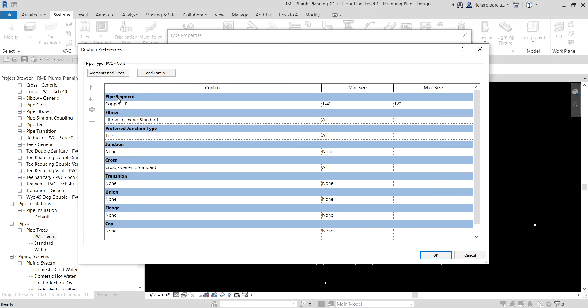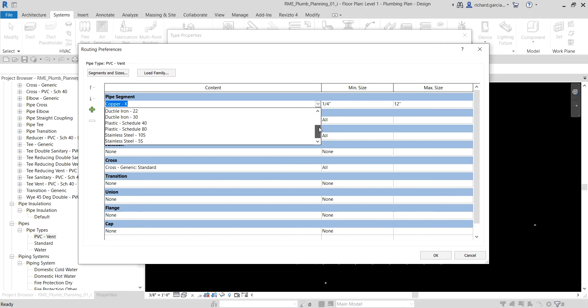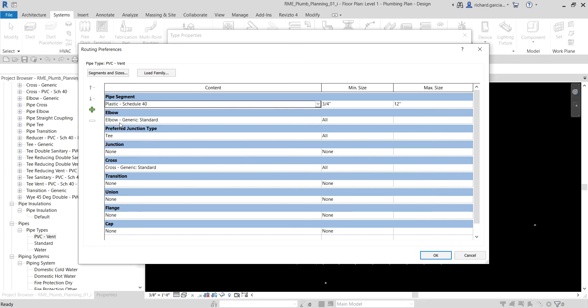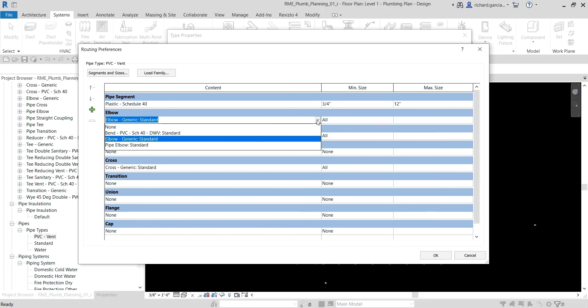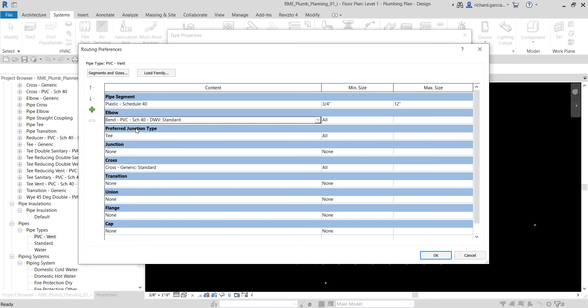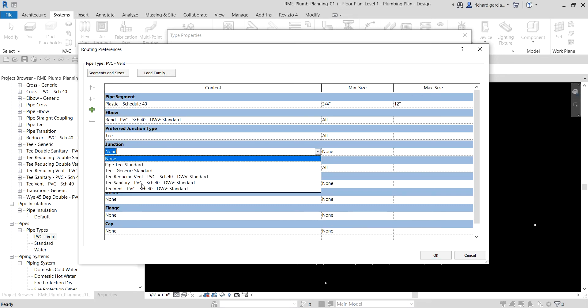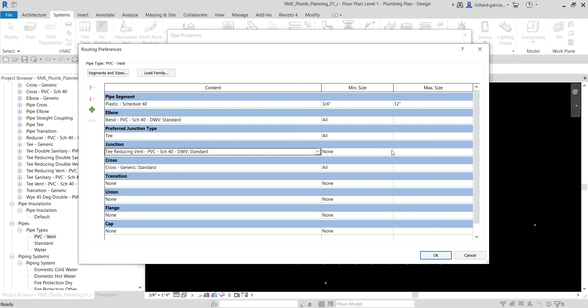In Routing Preferences, select the pipe segment you want for your PVC type from the drop-down. I'll select Plastic Schedule 40. You can also select the minimum and maximum size for that pipe type. For the elbow, I'll select PVC Schedule 40 Bend. For the junction, I want a tee junction — I'll select Tee Reducing Vent PVC Schedule 40 DWV Standard, setting the minimum size to All.